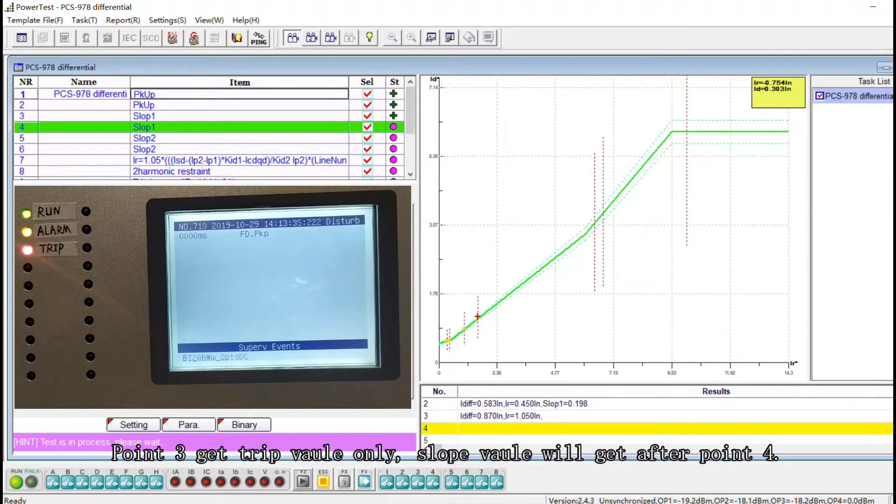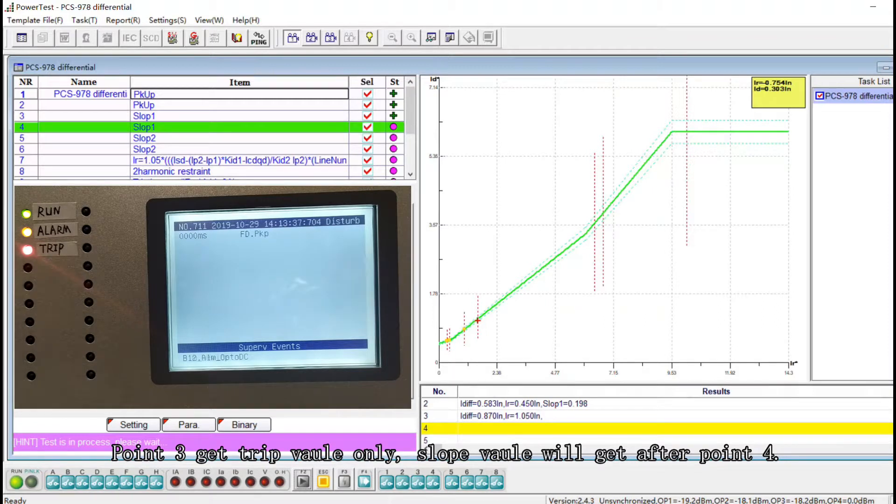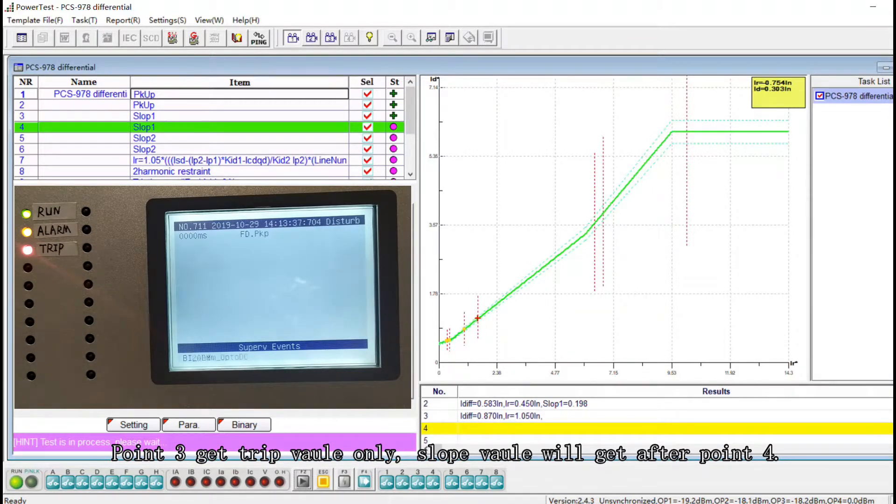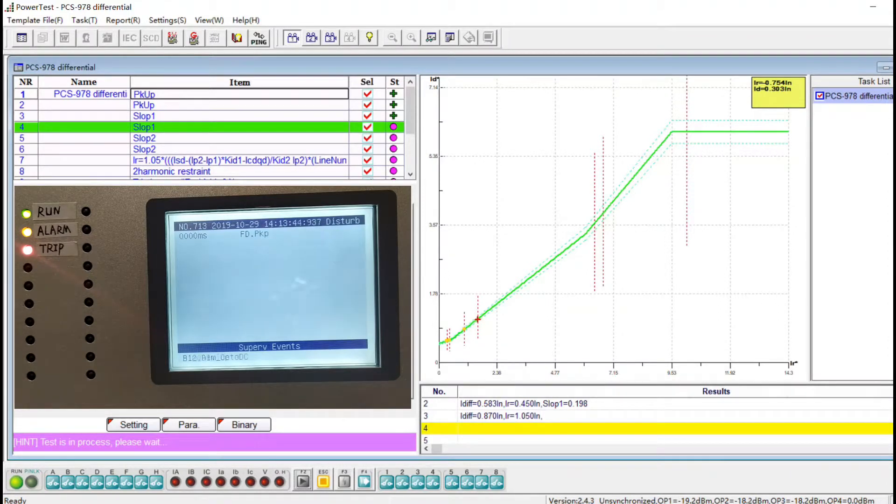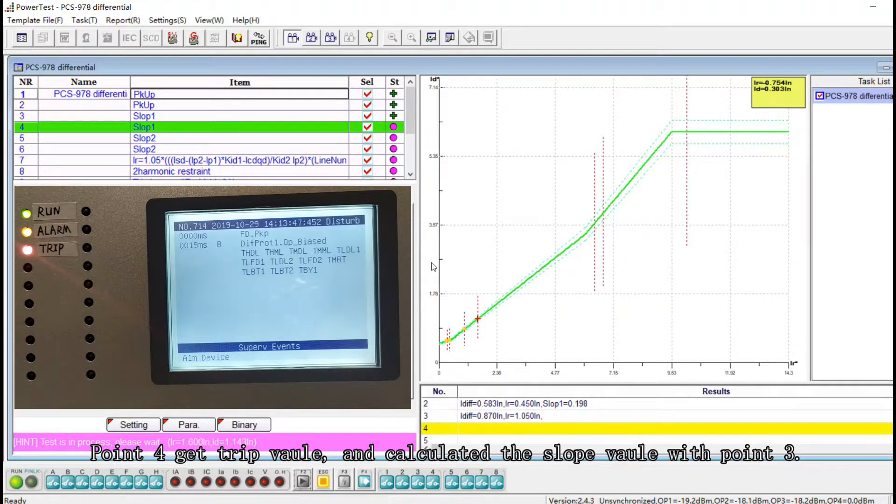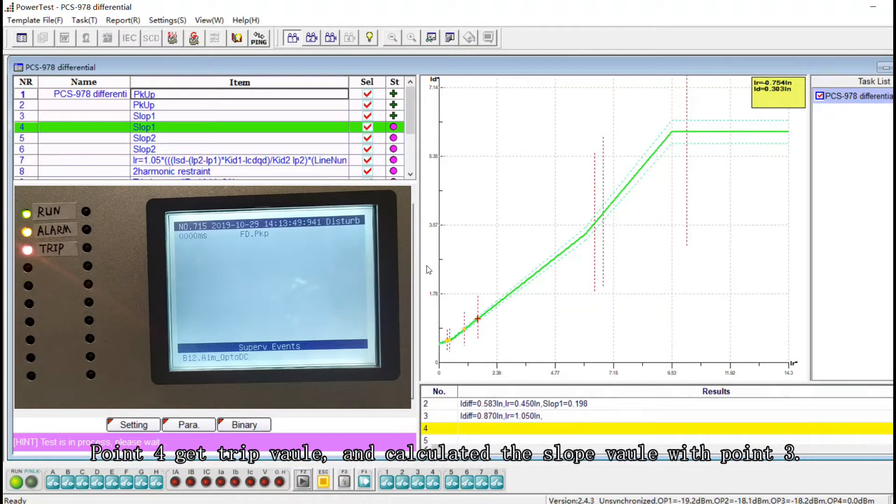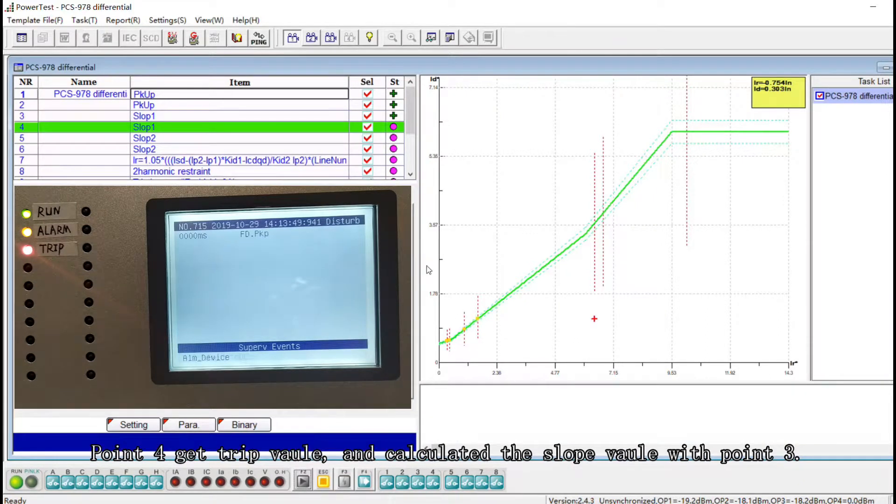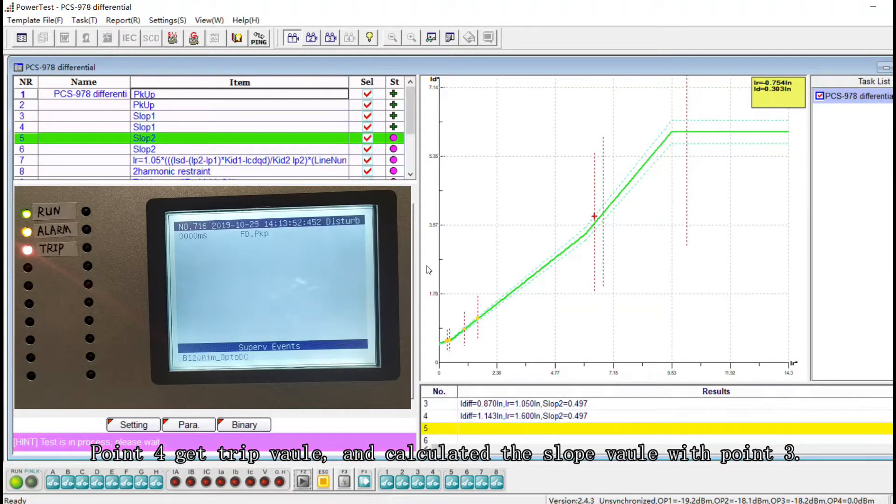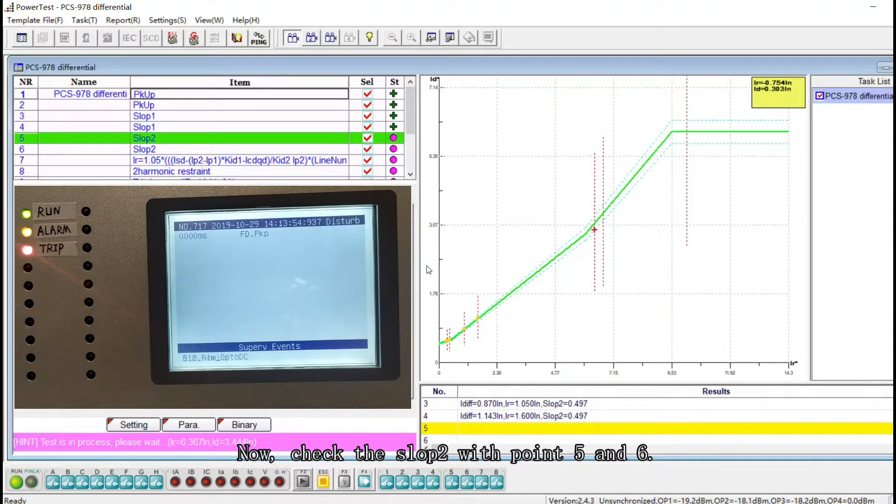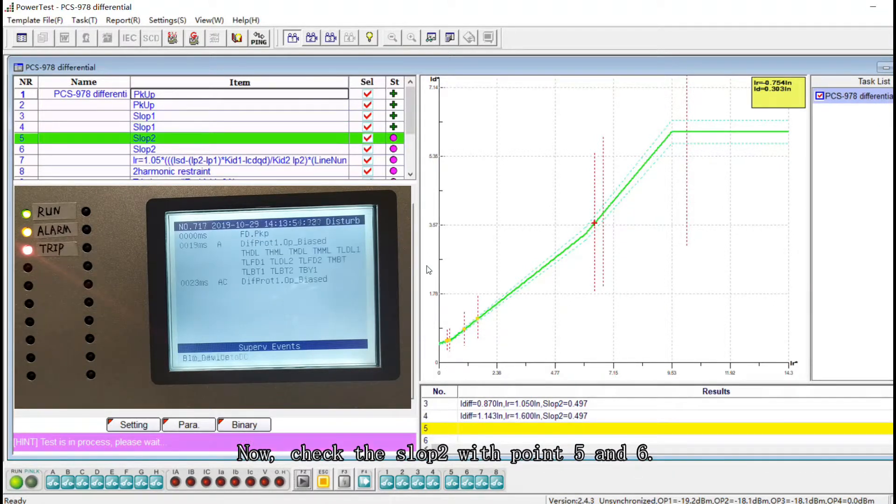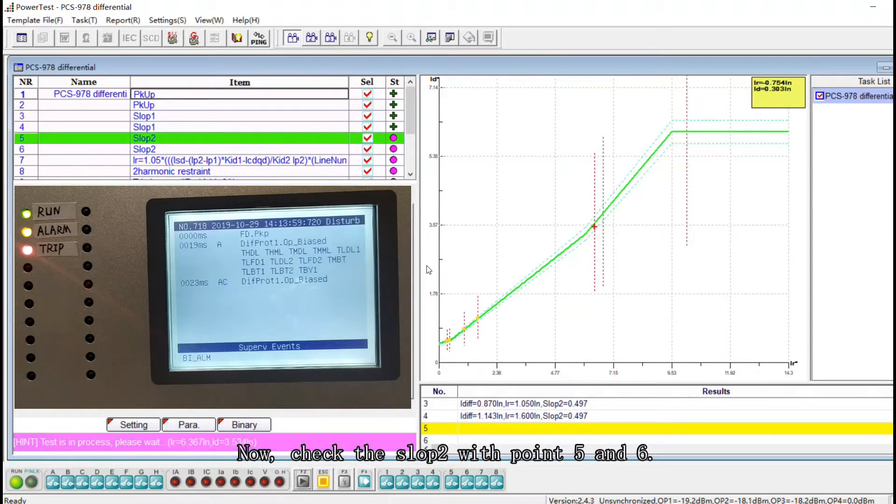Point three get trip value, only slope one value will get after point four. Point four get trip value and calculated the slope value with point three. Now check the slope two with point five and six.